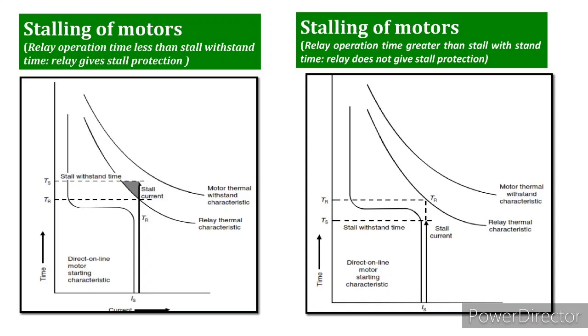Now we can see the stalling of motors, and understand more about that, on the left hand side. As you can see from the graph, it is about relay operation time less than stall withstand time, and the relay gives stall protection. You have the current on the X axis and time on the Y axis. There are two times: one is TS, the stall withstand time, and the other is TR. If TR is less than TS at this stage, you can say that the rotor is protected.